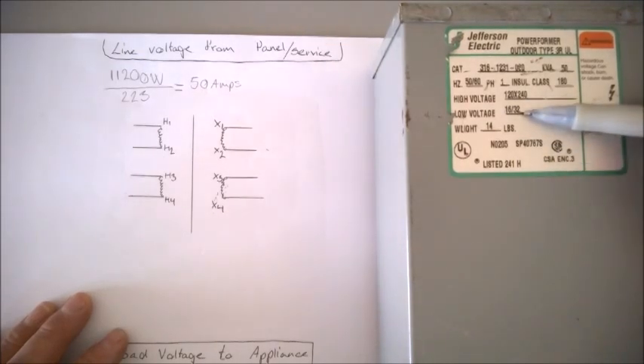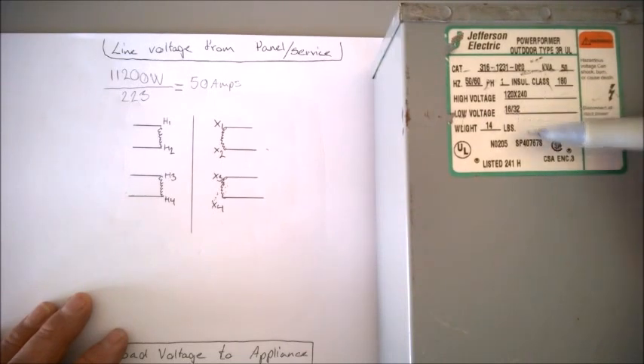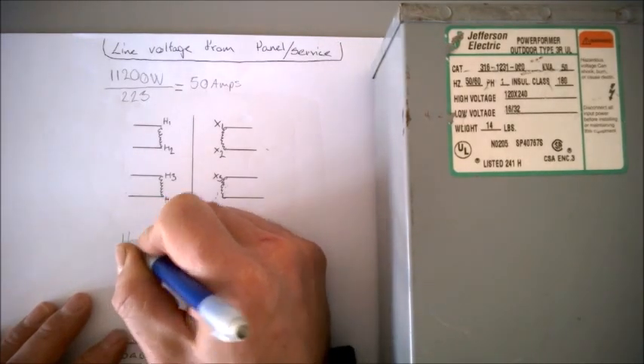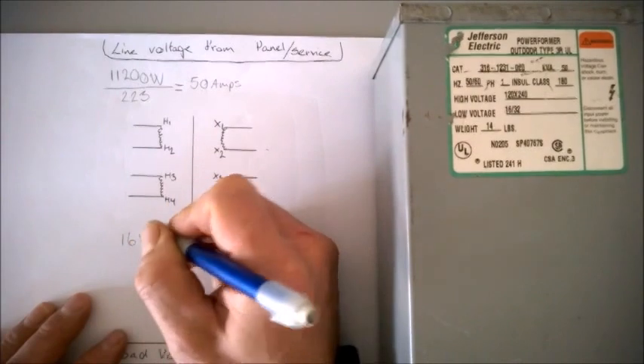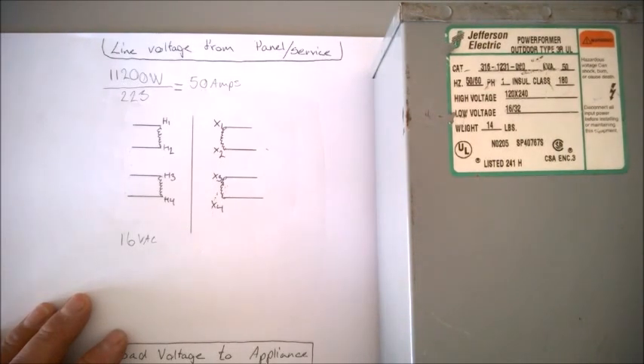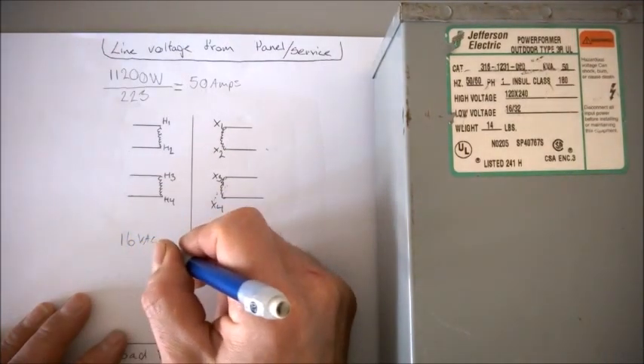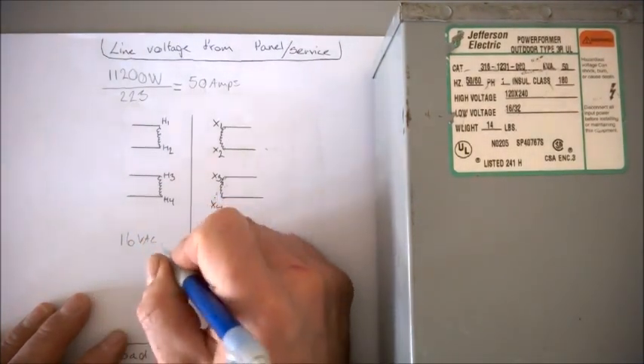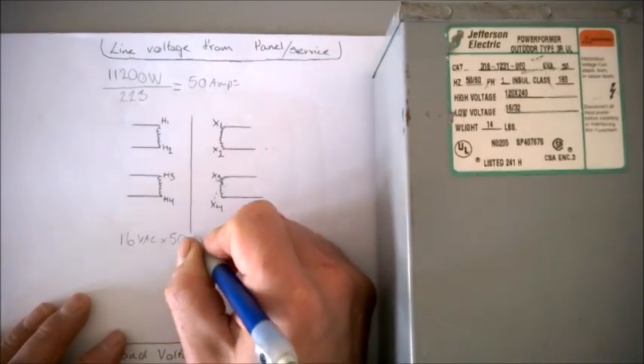Now back to this here, the 16/32. Depending on what kind of voltage you're going to be boosting with, in this case or bucking, let's take the 16 volts AC. That's what we want to boost it with. So if you're 208, we're going to be throwing it up to 224 in this configuration.